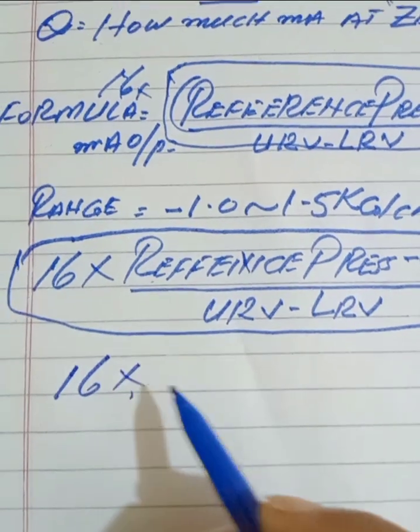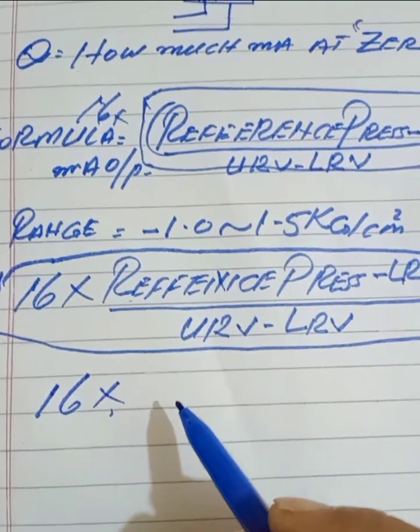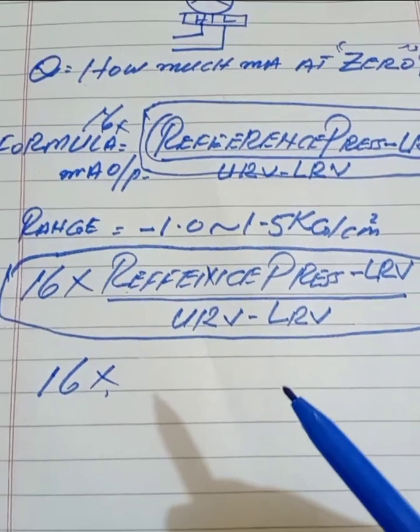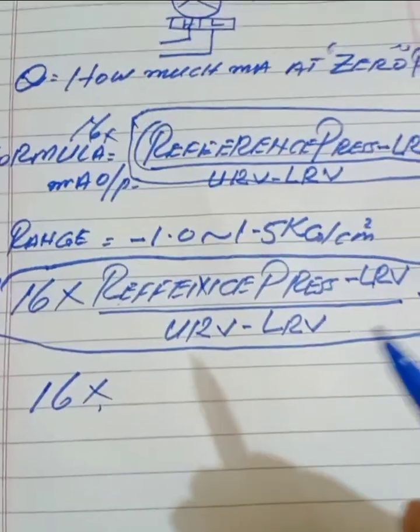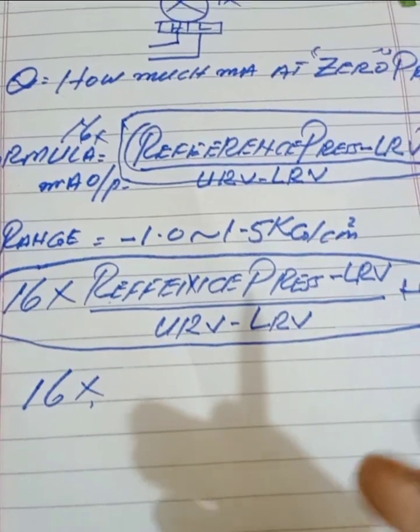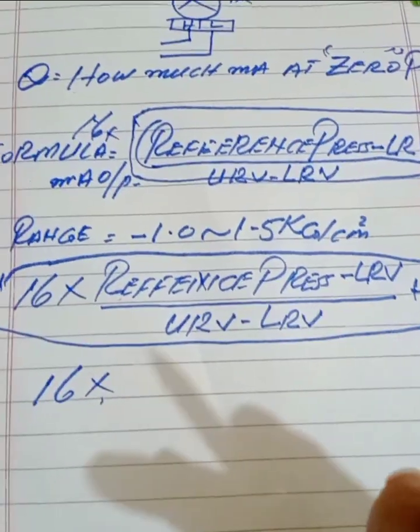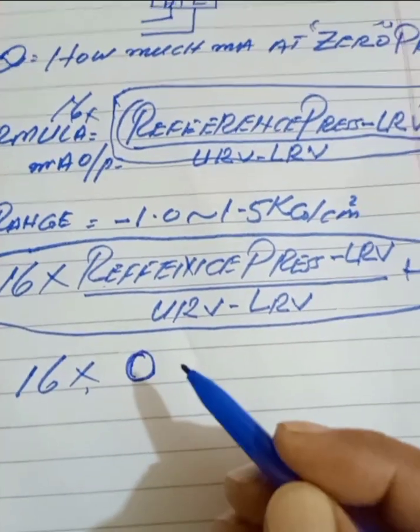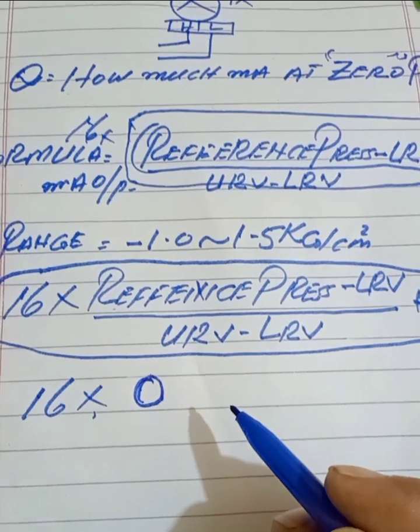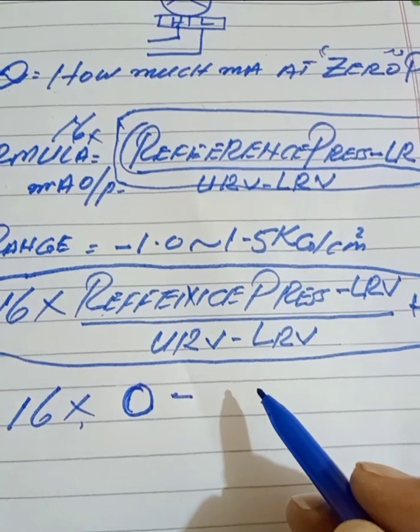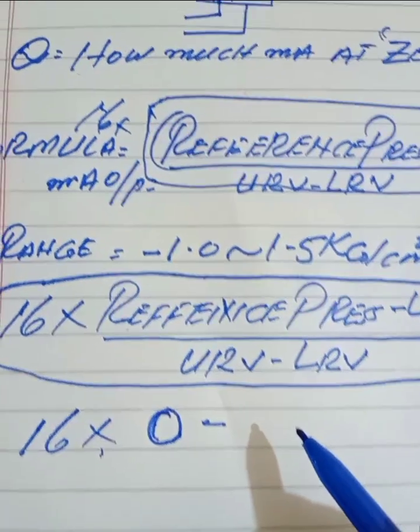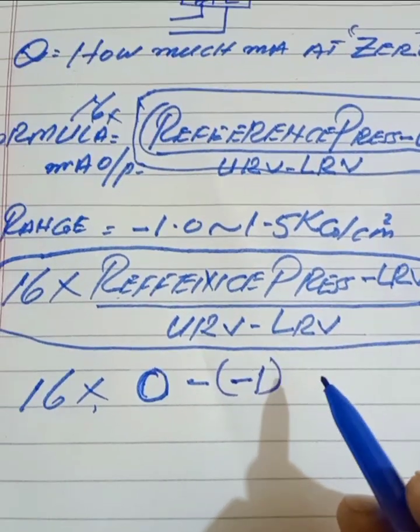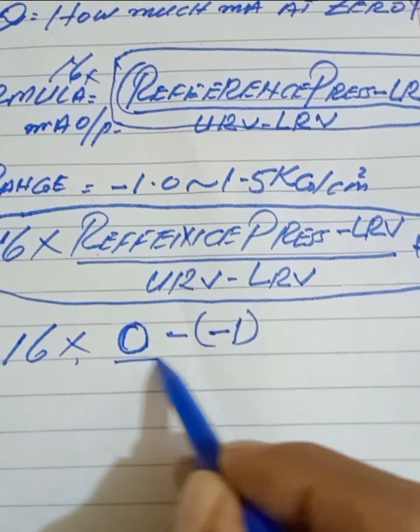We have 16 into our reference pressure. Suppose our transmitter, which has already been calibrated as an absolute pressure transmitter, is now under atmospheric pressure — either in the field or in the workshop after calibration. The atmospheric ambient pressure applied to the transmitter is zero. So our reference pressure is zero. Zero minus our LRV, which is minus 1.0. Our LRV is minus one.